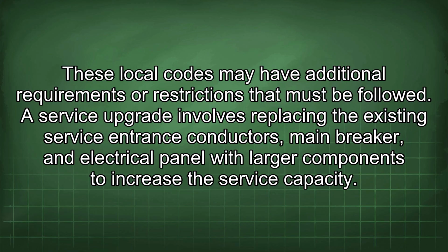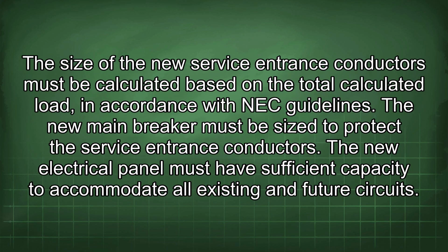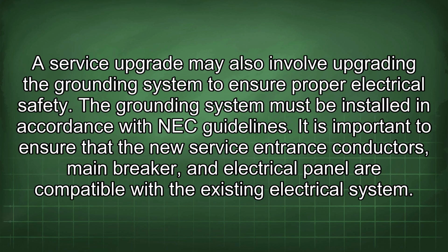A service upgrade involves replacing the existing service entrance conductors, main breaker, and electrical panel with larger components to increase the service capacity. The size of the new service entrance conductors must be calculated based on the total calculated load, in accordance with NEC guidelines. The new main breaker must be sized to protect the service entrance conductors. The new electrical panel must have sufficient capacity to accommodate all existing and future circuits. A service upgrade may also involve upgrading the grounding system to ensure proper electrical safety. The grounding system must be installed in accordance with NEC guidelines.